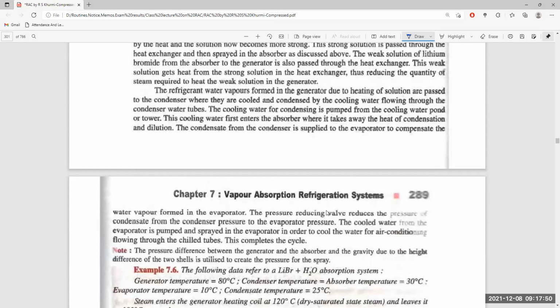The pressure reducing valve reduces the condensate from the condenser pressure to the evaporator pressure. The cooled water is pumped and sprayed in the evaporator in order to cool the water for air conditioning flowing through the chilled tube. This completes the cycle. So what is going on here? The refrigerant water vapor forms inside the generator.